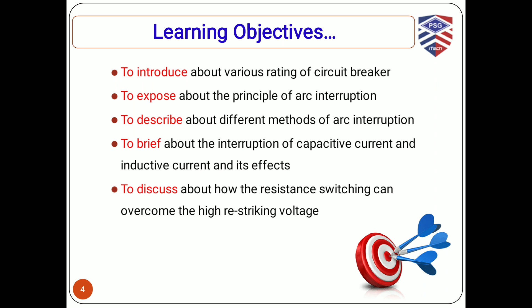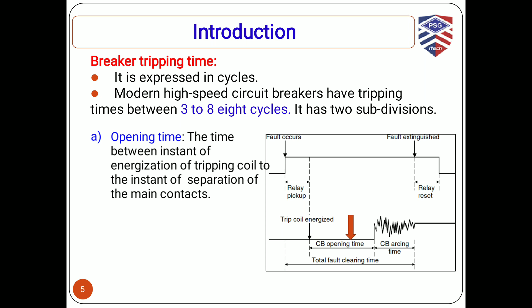So let's have a look at the tripping time of a circuit breaker. It is usually expressed in cycles. Modern high-speed circuit breakers have a tripping time of 3 to 8 cycles. It is divided into two subdivisions. The first one is opening time, shown in figure 2. It is the time between the instant of trip coil energization and the instant of separation of the main contacts. If the overall protection system recognizes that there is a fault, the relay of the protection system will start operating. The relay will pick up and energize the tripping coil to initiate the separation. So the time taken from the energization of the tripping coil till the instant of separation of the main contacts of the circuit breaker, we call the opening time.